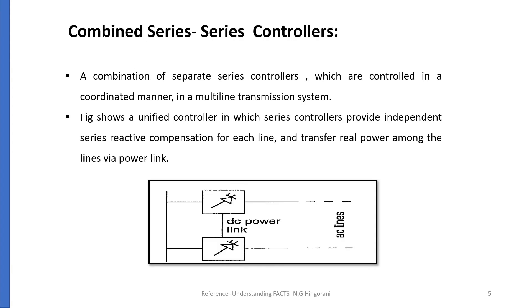Combined Series-Series Controllers could be a combination of separate series controllers which are controlled in a coordinated manner in a multi-line transmission system, or a unified controller. In this case, series controllers provide independent series reactive compensation for each line but also transfer the real power among the lines via the power link. Real power transfer capability of these controllers is referred to as interline power flow control. This makes it possible to balance both the real and reactive power flow in the lines, helping to maximize the utilization of the transmission system. The term unified here means the DC terminals of all controllers are connected together for real power transfer.